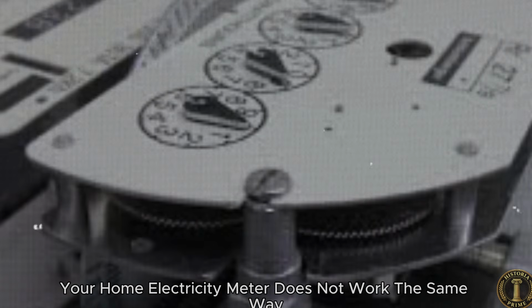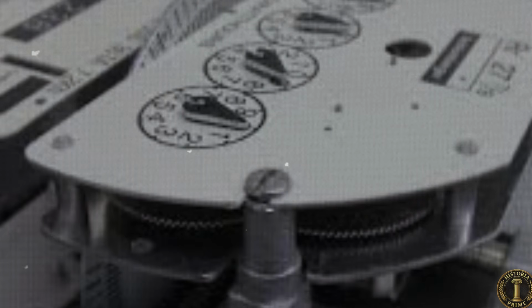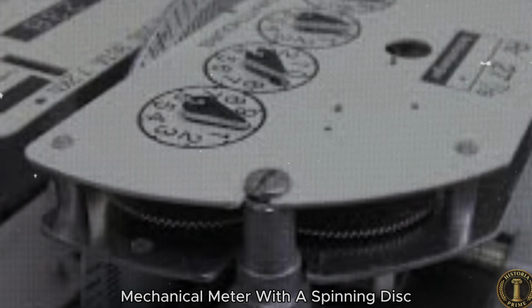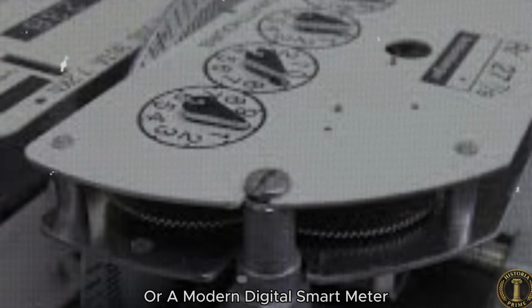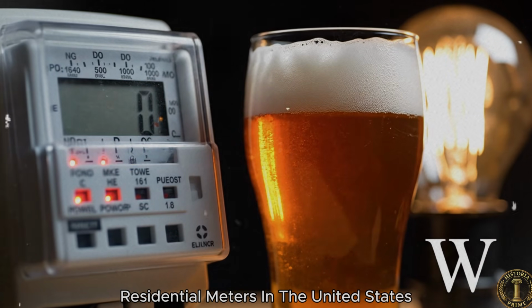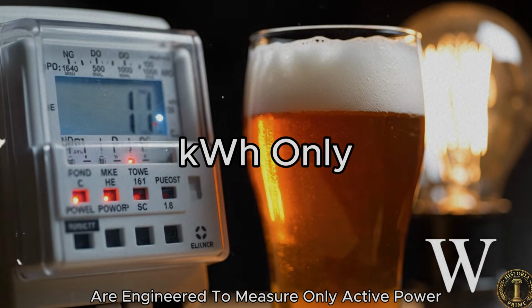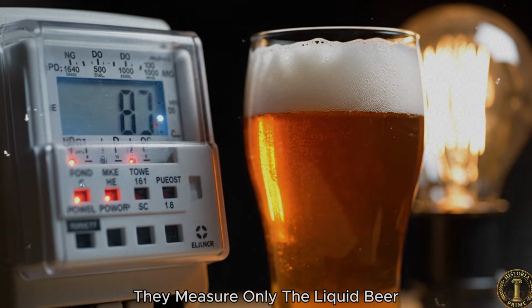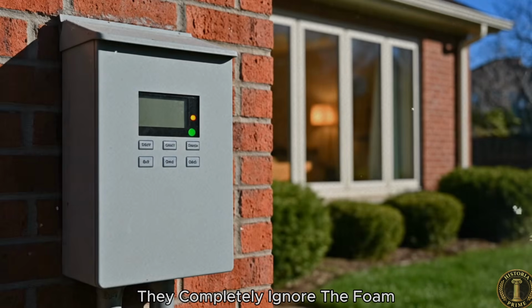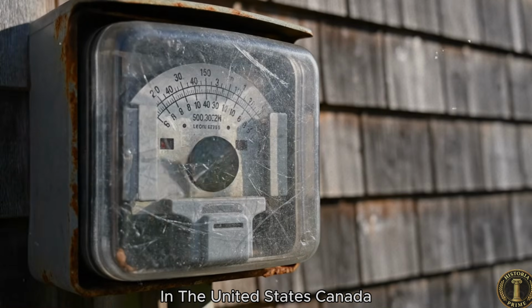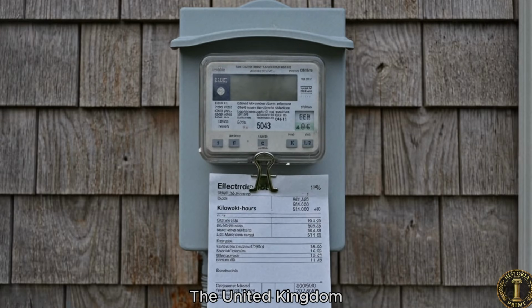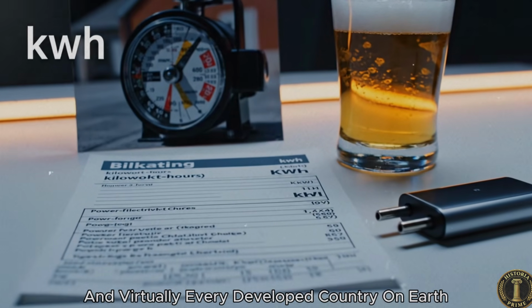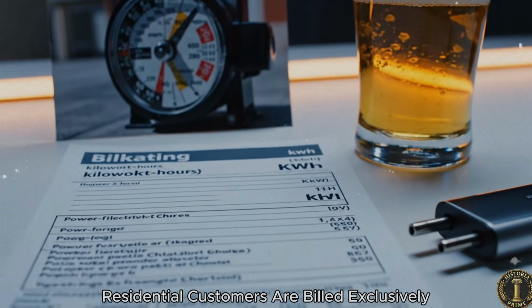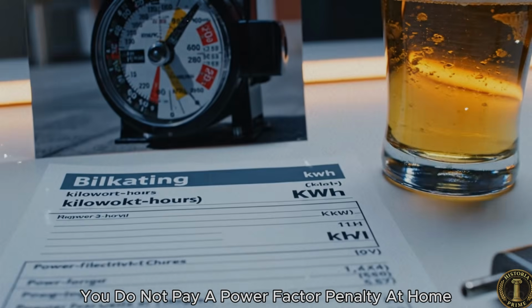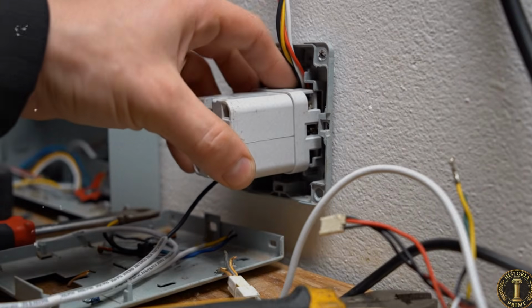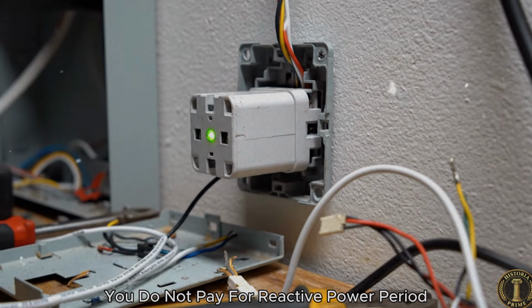Your home electricity meter does not work the same way. Whether you have an old-fashioned mechanical meter with a spinning disc or a modern digital smart meter, residential meters in the United States are engineered to measure only active power. They measure only the liquid beer. They completely ignore the foam. In the United States, Canada, the United Kingdom, and virtually every developed country on Earth, residential customers are billed exclusively in kilowatt hours. You do not pay a power factor penalty at home. You do not pay for reactive power, period.